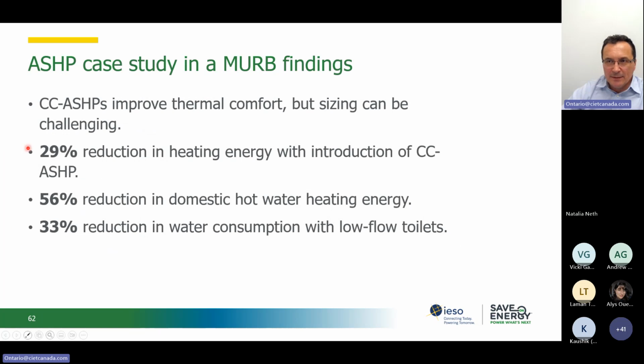I wouldn't say it's applicable to all projects, but just to have an idea of this example, we achieved a 29% reduction in the heating energy. We've seen a 56% reduction in domestic hot water energy by using heat pump technology there, and improving the efficiency of water use with low flow fixtures. There was an additional 30% reduction in water consumption.